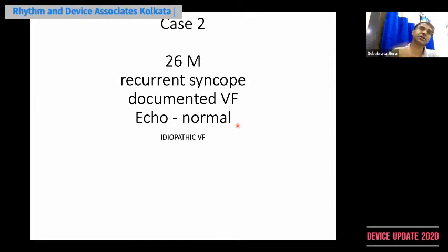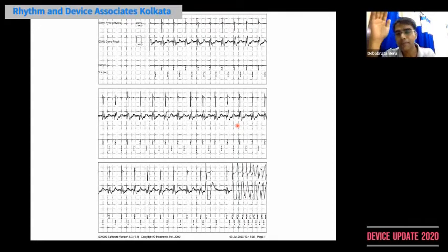Now, the patient comes with a shock. Again, our same question, whether the shocks are appropriate or inappropriate. So, this is the electrogram of the same patient. Let me show you. This is called EGM1 or the near field EGM. This EGM2 is CAN to coil, that means the far field EGM. And this is the marker channel. I wish any one of you can volunteer what has happened here. We can see in the marker channel that there is very fast annotation of an arrhythmia.